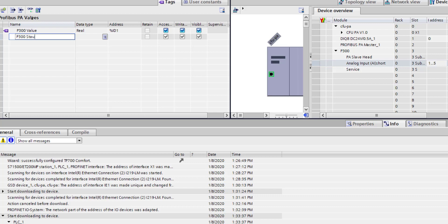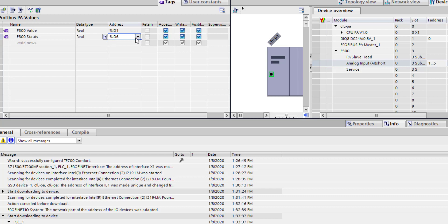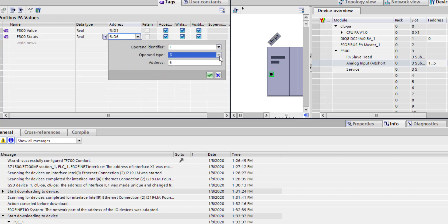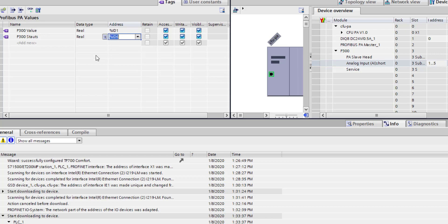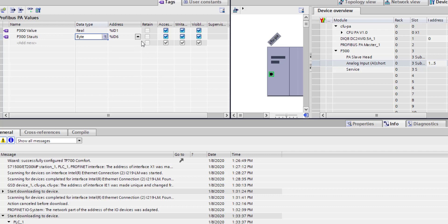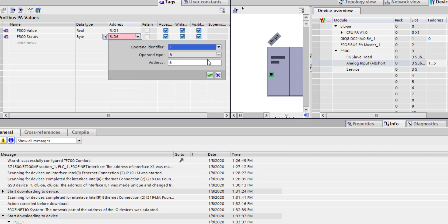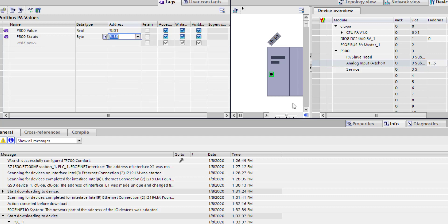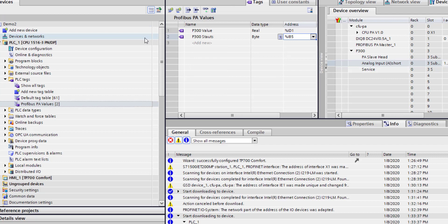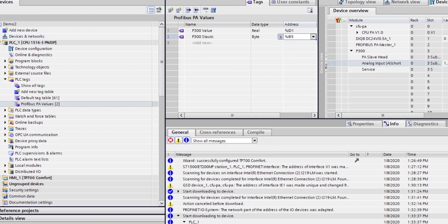P300_status - just need to put the right address in there. It's a byte, and it is the last part of that, which is five. That's the standard format for a PROFIBUS PA or DP process value. You get a real floating-point value and a status byte. Because this is all in the peripheral memory area, I don't have to use any special blocks like DP_READ or DP_WRITE - those are going to be coming straight back into the PLC with no additional functions required.